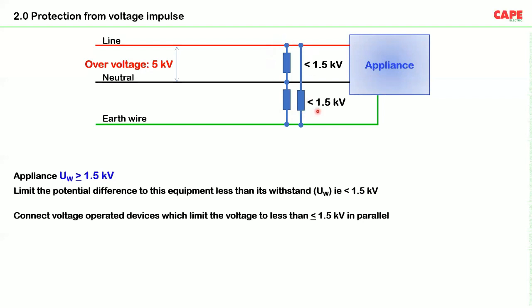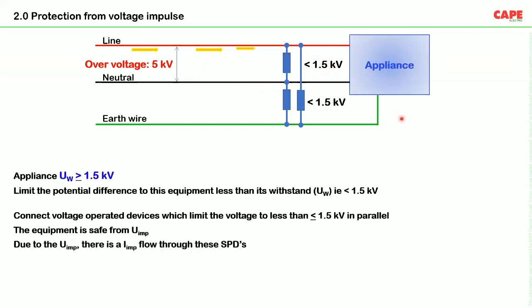And these devices have a parameter called voltage protection level, which is the voltage to which the device is able to limit higher voltages. Imagine we have 3 devices connected in these lines, and these are able to limit the voltage to 1.5 kV. So once the overvoltage reaches this equipment, the devices are able to clamp the voltage to 1.5 kV. As a result, your appliance is safe, but due to this clamping, the current which is supposed to flow will flow through the SPD and it gets distributed throughout the line.